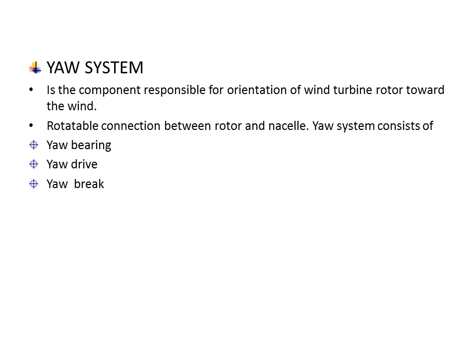Next, see what is yaw brake. To stabilize the yaw bearing against rotation, braking is necessary, meaning a constant small counter torque is applied at the yaw drive. But this constant torque reduces the reliability of the electric yaw drive, so a hydraulically actuated disc brake is commonly used.